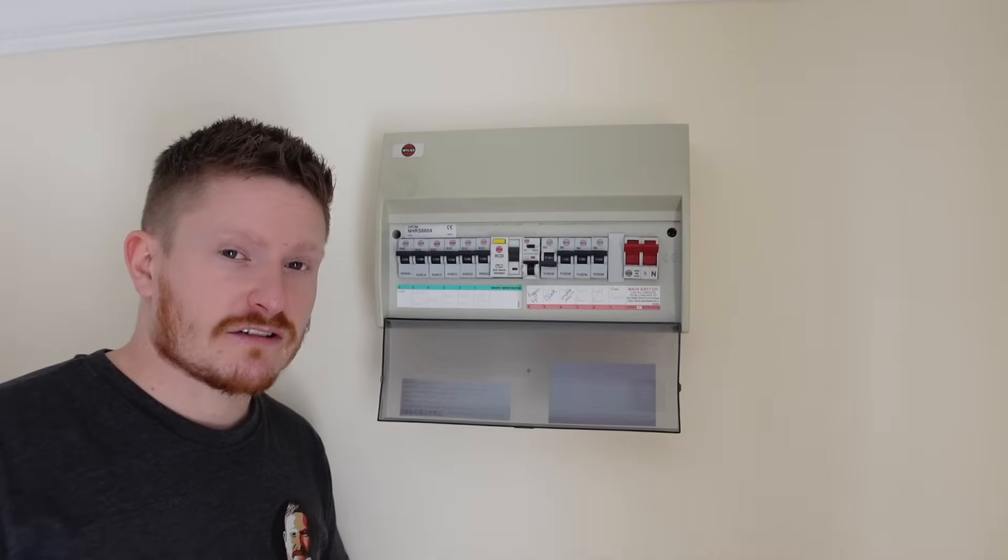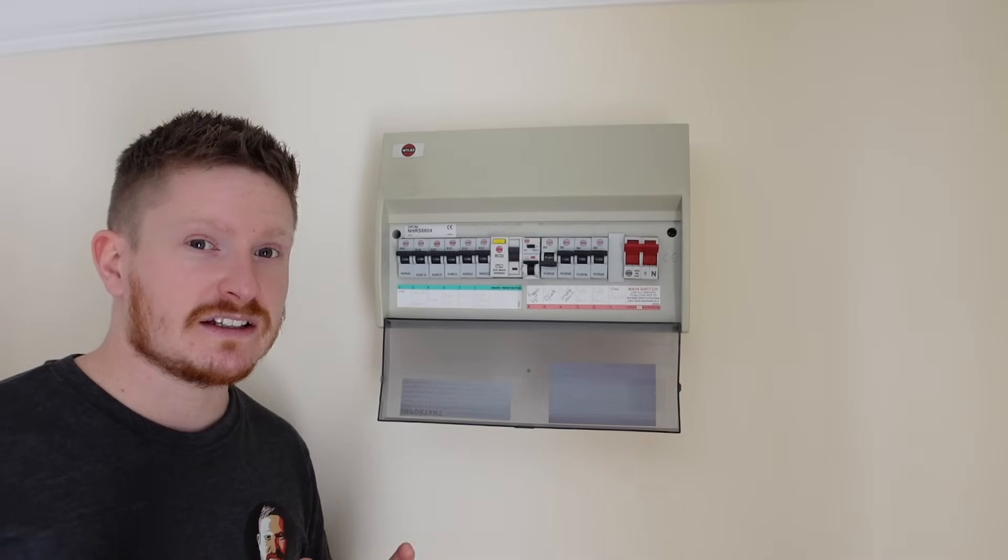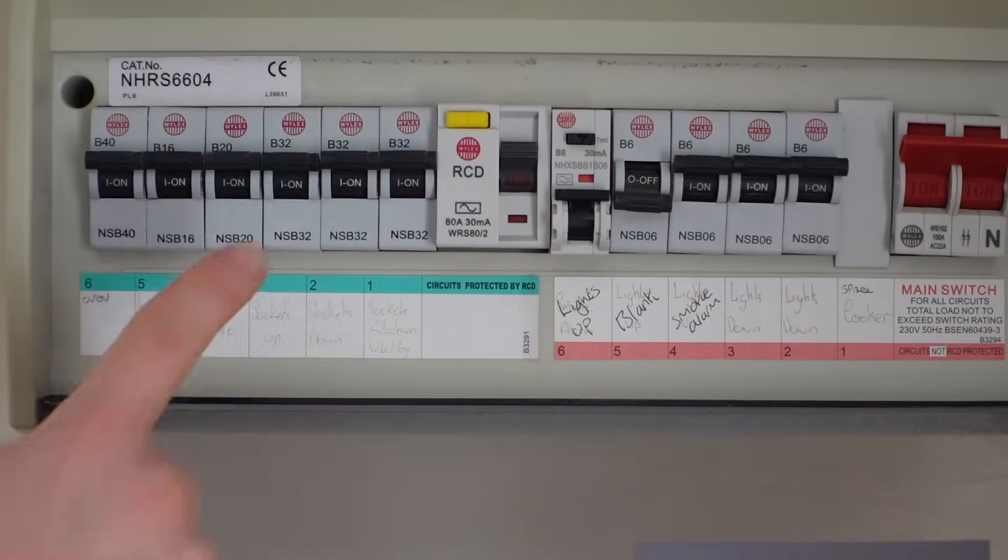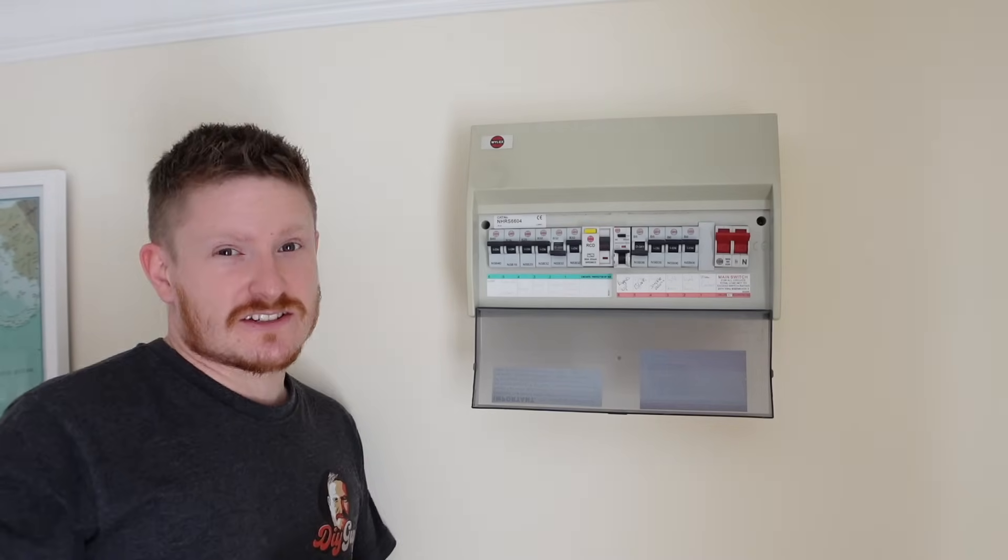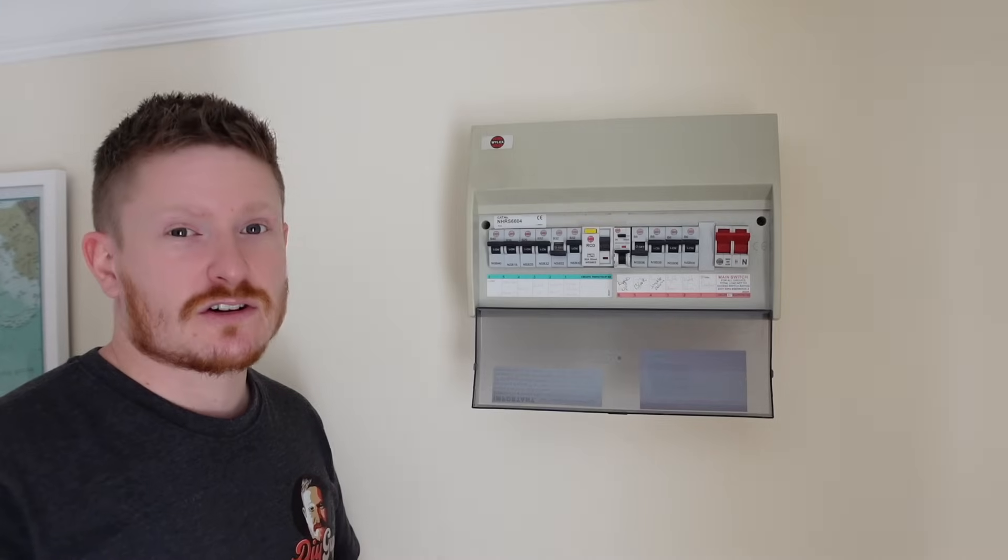Let's hope it's labelled up correctly and we'll turn off this 32 amp breaker just here labelled sockets down. If you listen in the background you can still hear our socket tester ringing away so we should hopefully hear that socket tester turn off. Okay, so you can hear the socket test has gone off so we're pretty confident that the power has gone off to that socket we're working on.